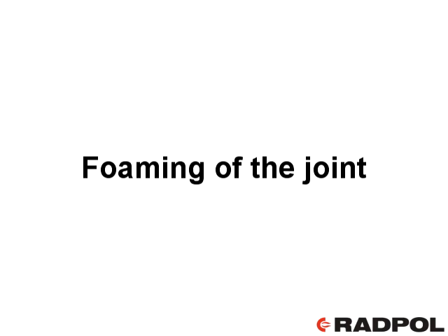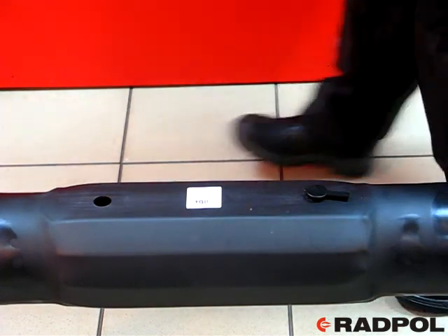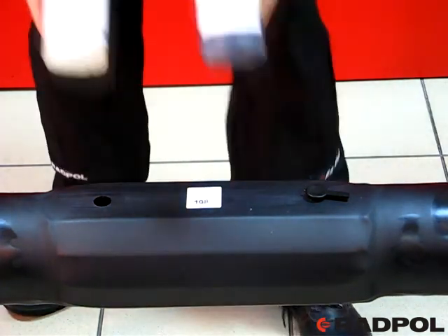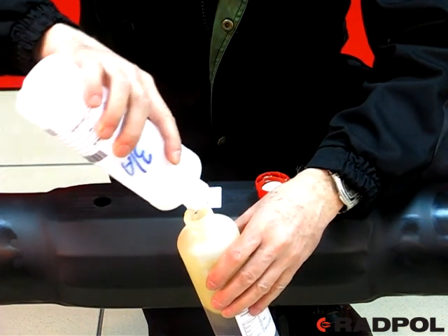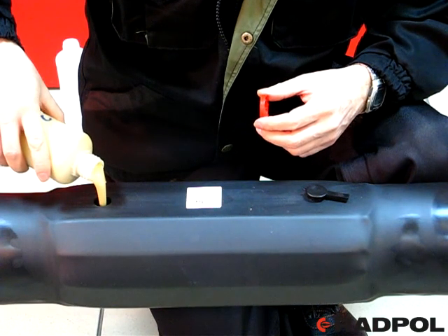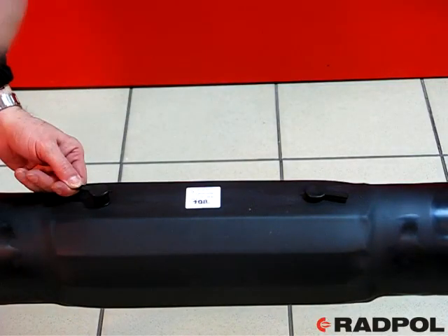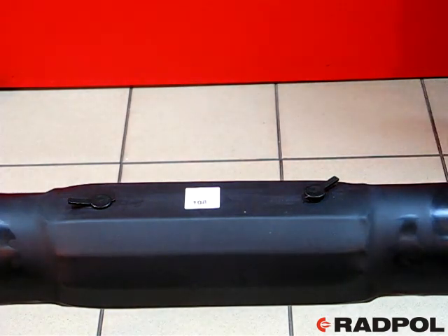Foaming of the joint: hammer in one of the venting plugs and foam the joint according to the producer's guidance. Make sure you follow the advice concerning the right temperatures. In case of two-liquid foams recommended by Radpol, join together the contents of both containers and next, by multiple shaking, mix both components. The mixture formed should be quickly poured into the remaining foaming hole. Hammer in the second venting plug. The bulging foam should fill up the interior, and the accompanying chemical reaction should warm up the joint.